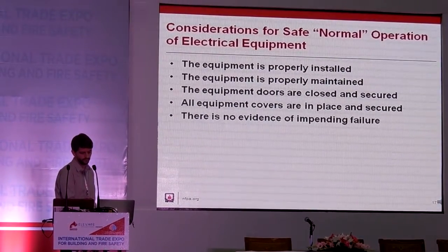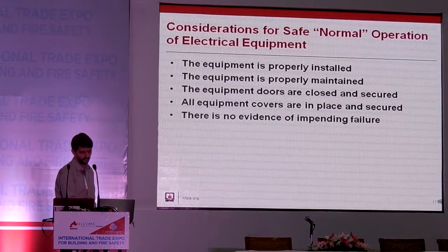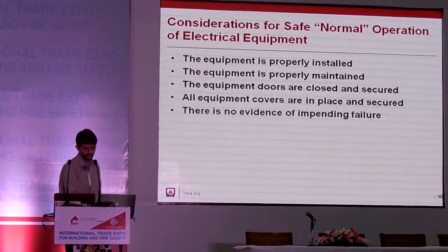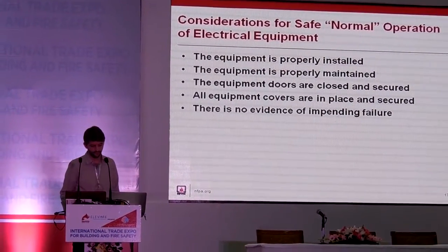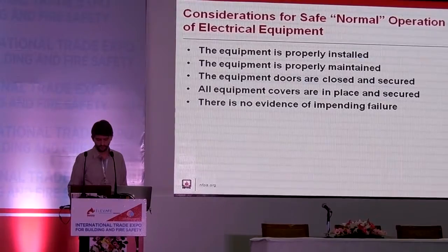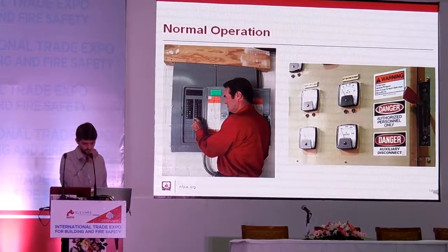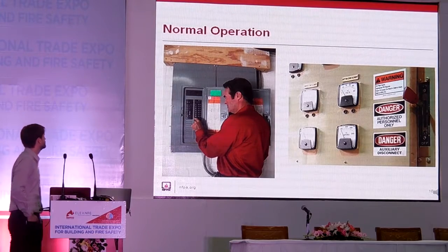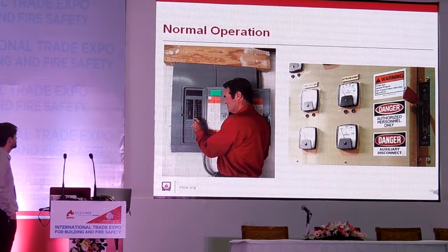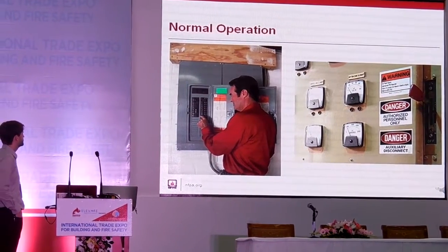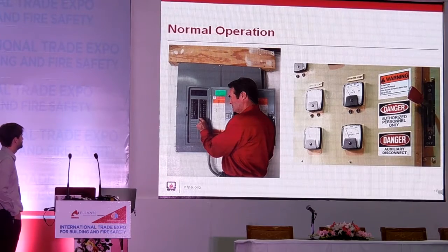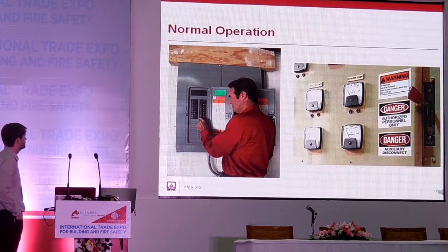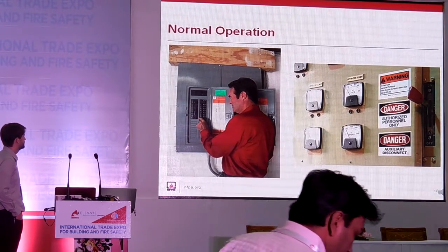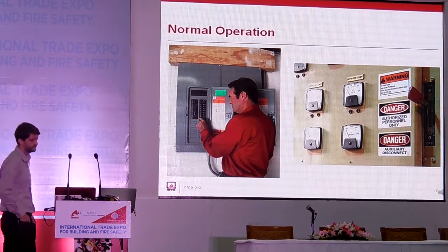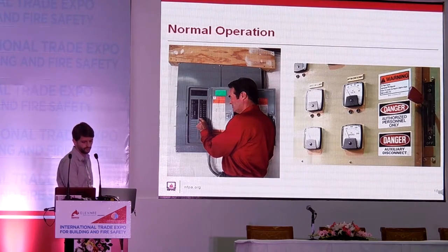Is there indication that the equipment has experienced high temperature? These are considerations that must be looked at in order to ensure that the equipment is going to function as intended. Operation of the circuit breakers, as shown in the photograph on the left, or the disconnecting means handle, as shown in the photograph on the right, is considered to be normal use for those types of electrical equipment, where assurances of proper installation and proper maintenance and no impending failure can be made.